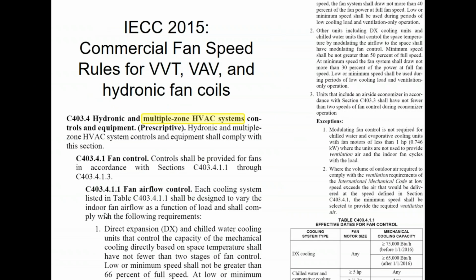All right, in addition to the multiple stages, you may also have to have multiple fan speeds. You may have to control those as well. We talked about this last week too, and this is one of the last few things that repeat from last week, and then we'll be on to all new stuff. Section 403.4.1.1, fan airflow control, is unfortunately accidentally stuck under the hydronic and multi-zone HVAC systems. That gets corrected in the IECC 2018, and it gets its own section. But for 2015, which is what we're doing right now, it is under that section, so it only applies to hydronic systems or multiple zone systems.